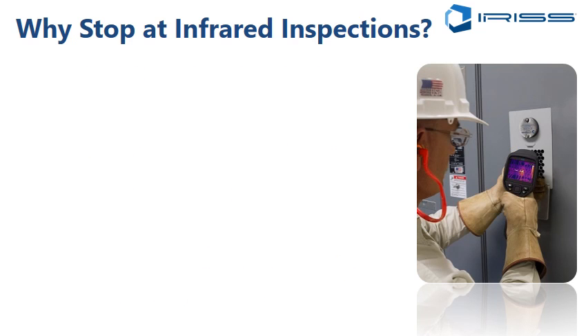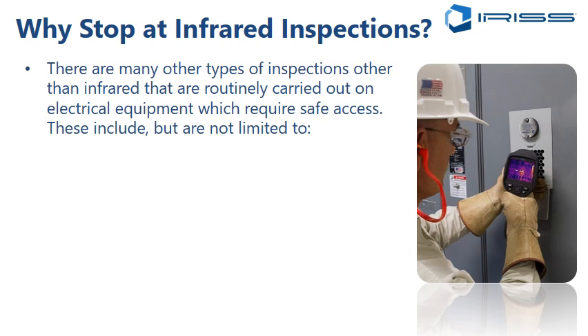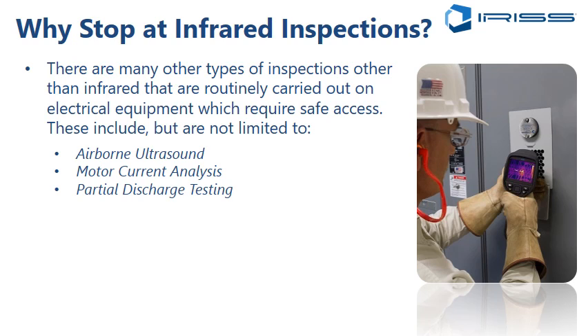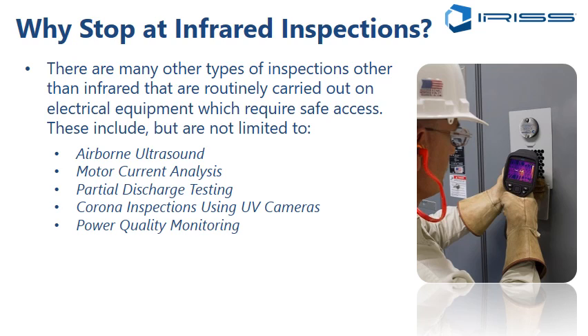So what we started to think about is, why stop at infrared inspections? An infrared window makes you just think it does infrared inspections, but there are many types of inspections that we have to do other than infrared, and these include but are not limited to the following: airborne ultrasound. So we need to apply access for ultrasound equipment, motor current analysis, partial discharge testing, corona inspections using UV cameras, power quality monitoring, and not last but not least, the visual inspection.